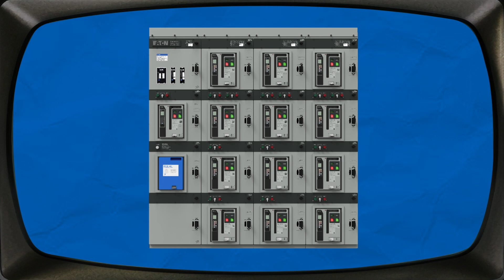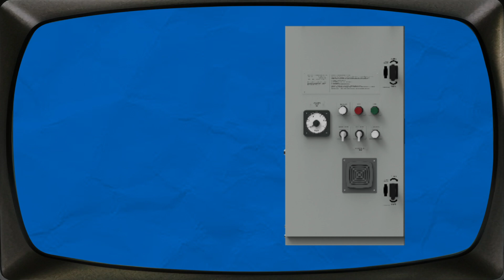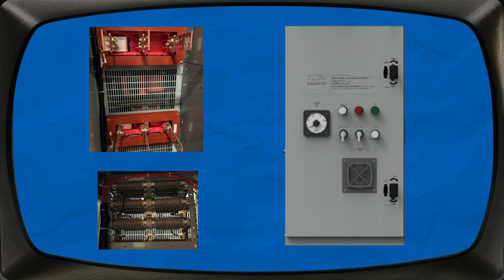Next is the high-resistance grounding, or HRG, compartment that contains the relays, alarms, and lights necessary for the grounding system. Typically, the only two items not in the compartment are the metering transformers and the grounding resistor, which are usually located in the cable section.